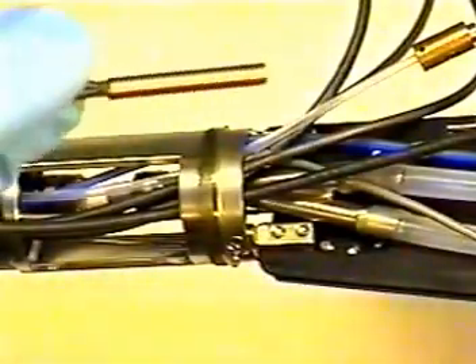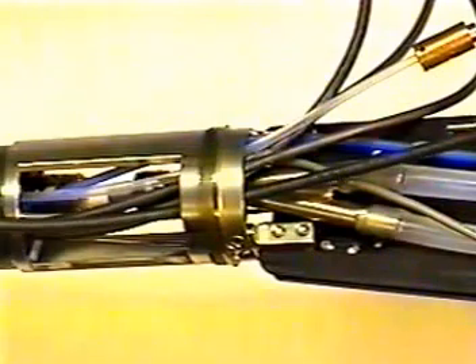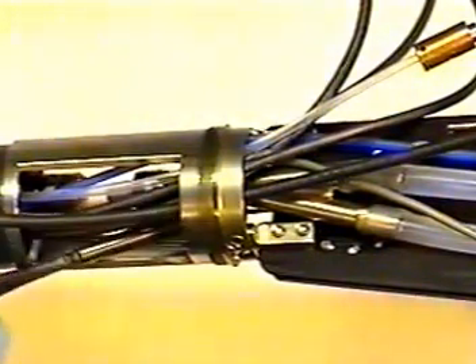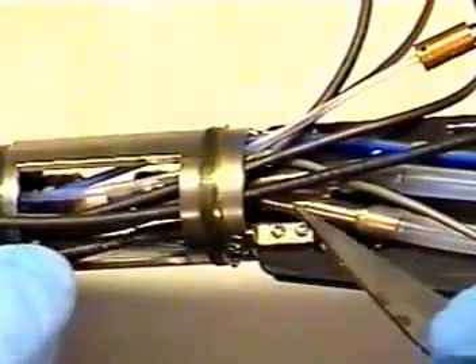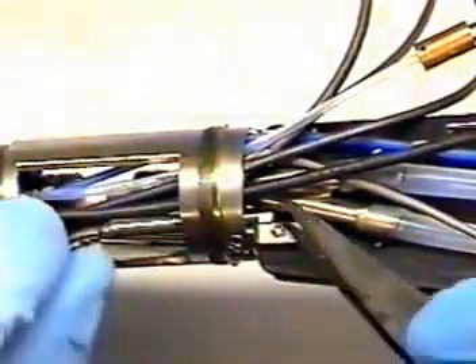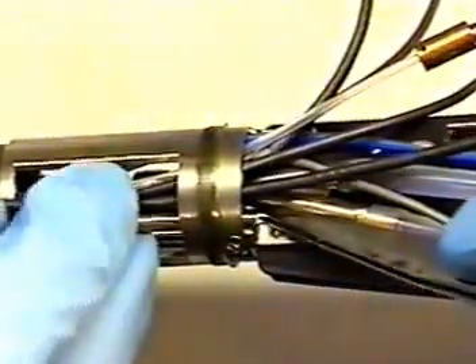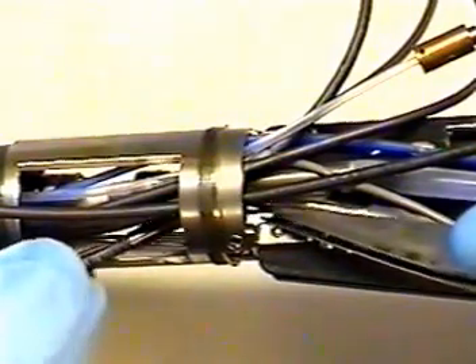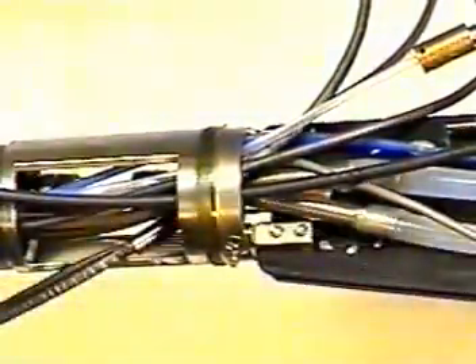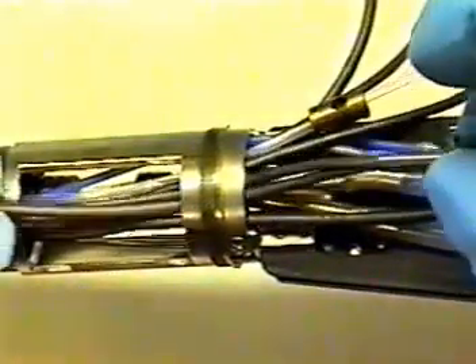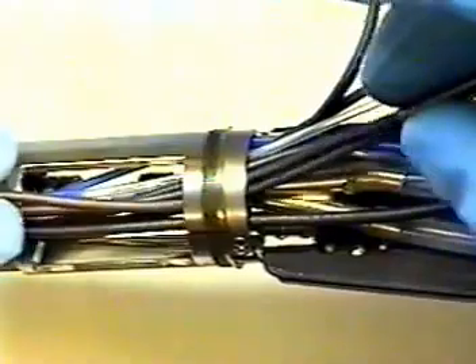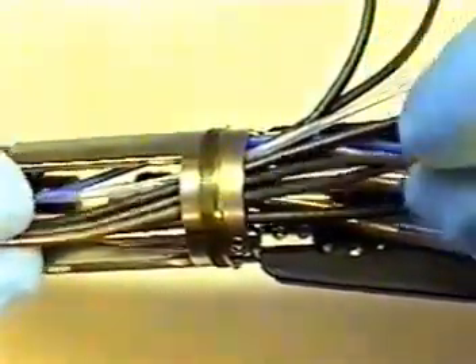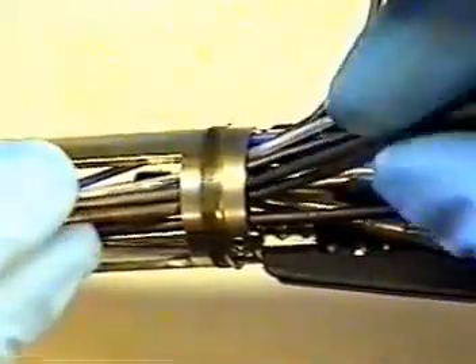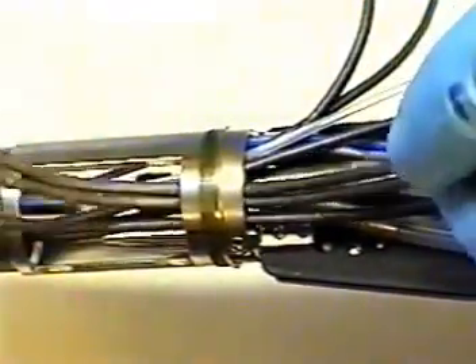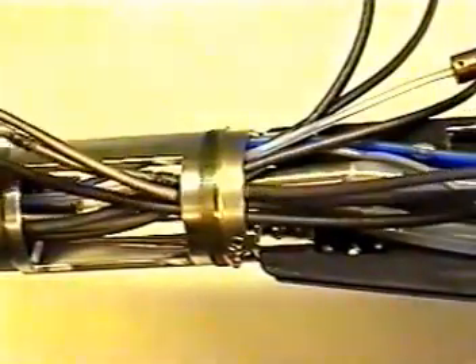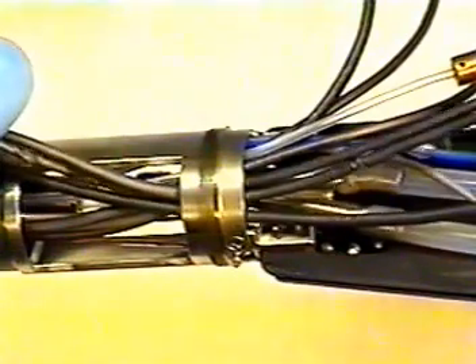Next step is to feed through light guide bundle, illumination bundle, through endoscope, being extremely careful. You can use tweezers to guide light guide bundle through body section. When pulling through light guide bundle, be extremely careful not to kink, bend, push, or put any force on gray illumination bundle, otherwise it will damage the light guide bundle. Pull light guide bundle through all the way, coil up, and keep to one side.